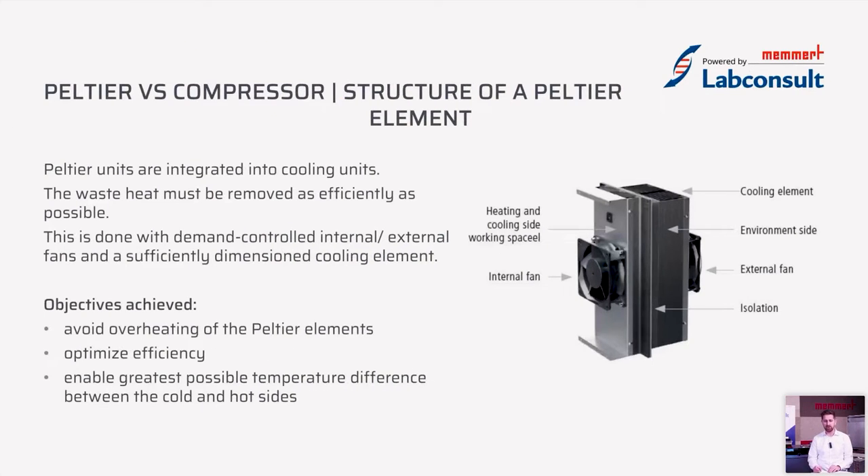The Peltier chips are integrated in Peltier modules, which you can see in this picture. This is a picture of the Peltier modules we're using in our latest models HPP eco and IPP eco. The waste heat created must be removed as efficiently as possible to ensure the best energy consumption, improve temperature stability inside the chamber, and provide the best possible environment for your samples. This is done with demand-controlled fans on the inside and outside, which speed up and slow down based on the temperature difference between the environment, the chamber interior, and the set point.